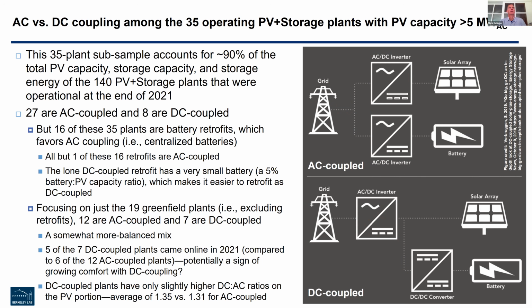But you need to consider that 16 of these 35 plants involve battery retrofits — the battery added to a standalone PV plant after it had been operating for some time. That type of retrofit typically favors AC coupling, because you can install the batteries in one centralized location rather than going back into the array to scatter batteries next to each individual inverter.